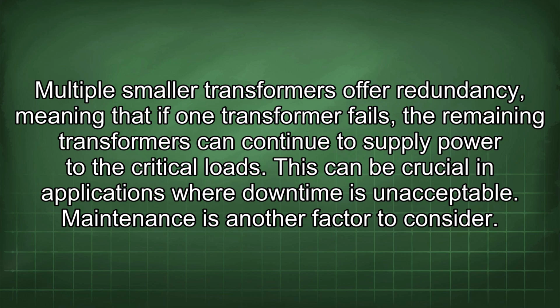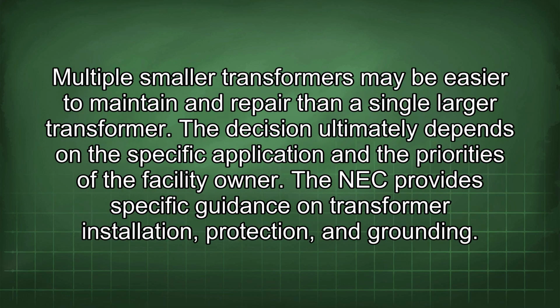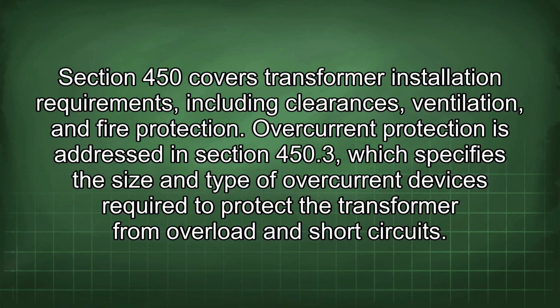Maintenance is another factor to consider. Multiple smaller transformers may be easier to maintain and repair than a single larger transformer. The decision ultimately depends on the specific application and the priorities of the facility owner. The NEC provides specific guidance on transformer installation, protection, and grounding. Section 450 covers transformer installation requirements, including clearances, ventilation, and fire protection.